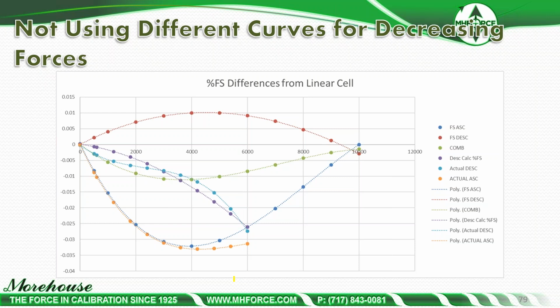Hey, if I just load it to 50%, what happens on my curve? If I load it to 100%, what happens on my curve? And it kind of looks like a whale. So you kind of call it the whaley, but you can see what's going on. The only thing you can really do in this case, if you're using a load cell with decreasing or descending forces, is use a combined curve.